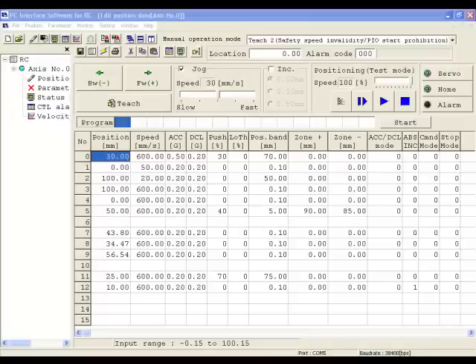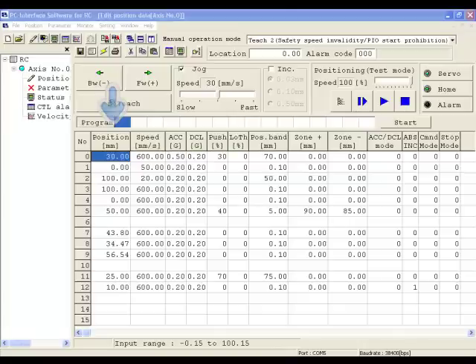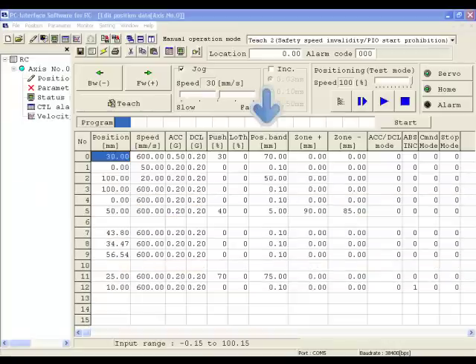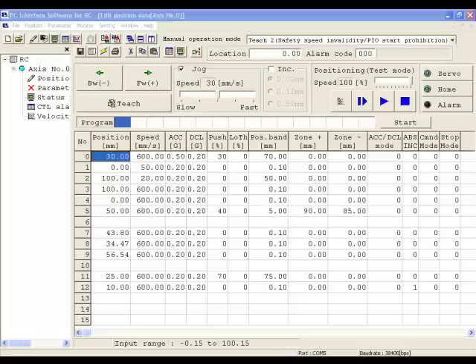Using the RoboCylinder PC software, the position information is stored inside the position table. Each position gets a unique position number. The first column of the position table represents the location value, in millimeters, the actuator will move to. In positioning mode, the actuator will turn on a position complete output, PEND, when the actuator has reached within the position band of the target position. The position band defaults to 0.1 millimeters, meaning the position complete will come on when the actuator is within 0.1 millimeters of the target location.